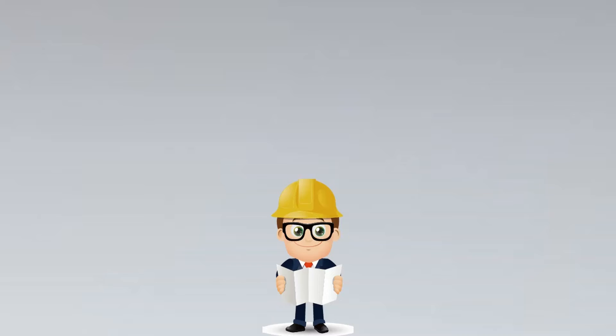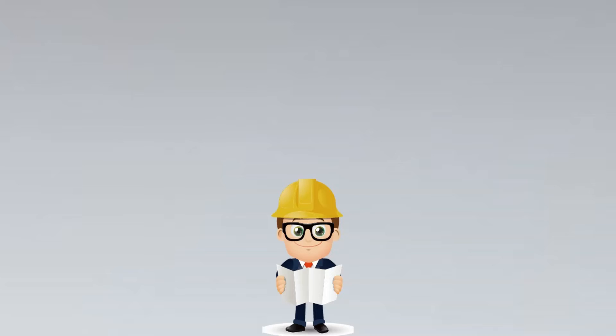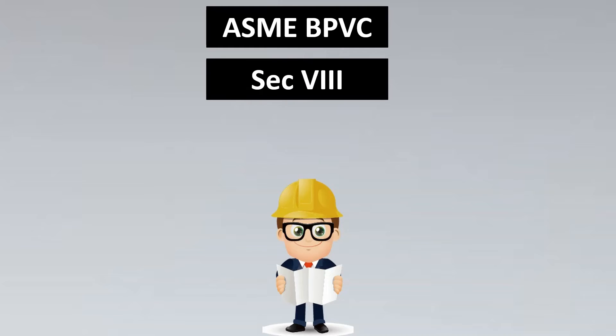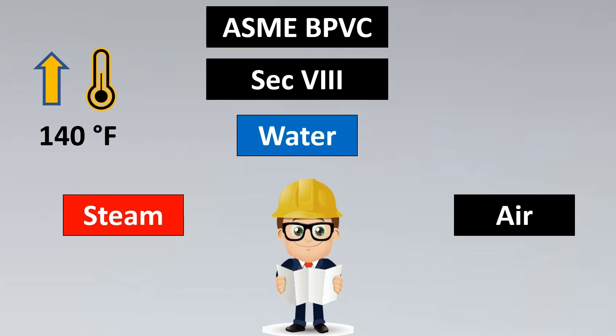Now you might ask: for which liquids can we use this? Can we use this for toxic services? The answer is that a lever is never preferred for toxic services, because the operator might not want the fluid to be relieved out. So for which services is a lever usually used? According to ASME Section 8, whether it is steam, water, or air with a temperature greater than 140°F or 60°C, these services should have a lever with the relief valve.